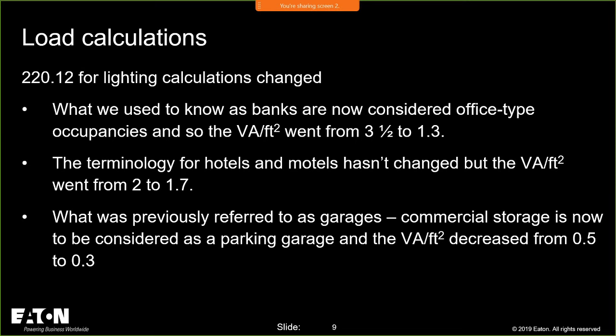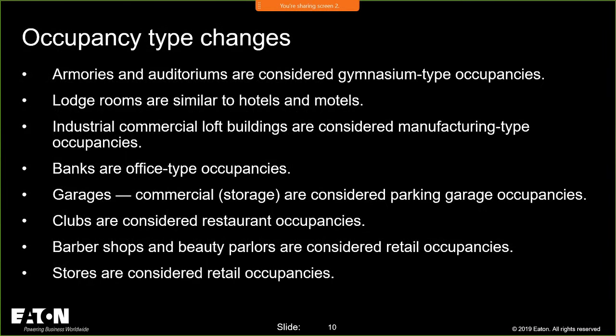Hotels and motels hasn't changed, but the VA per square foot went from 2 to 1.7. So that's an example where your VA per square foot went down, which will probably lead to smaller feeders and services. And then what was previously referred to as garages, which is now commercial storage, is now to be considered as parking garage. And again, that went from 0.5 to 0.3. So you'll notice in the bottom of the table, in the footnotes to that table, we basically took all of what was in 220.12 in the past, any of those occupancy types that changed, we gave you a footnote to tell you, here's what we used to call it, and here's what we call it today.